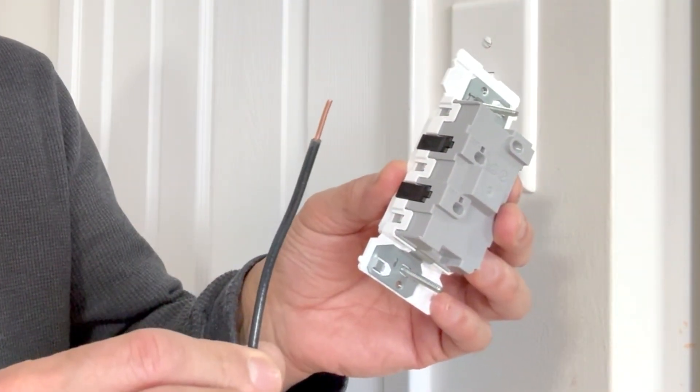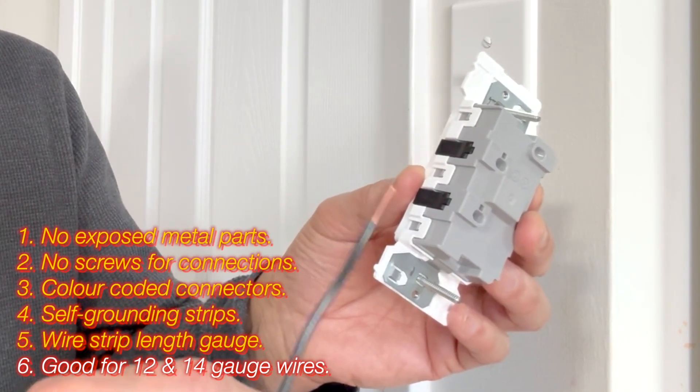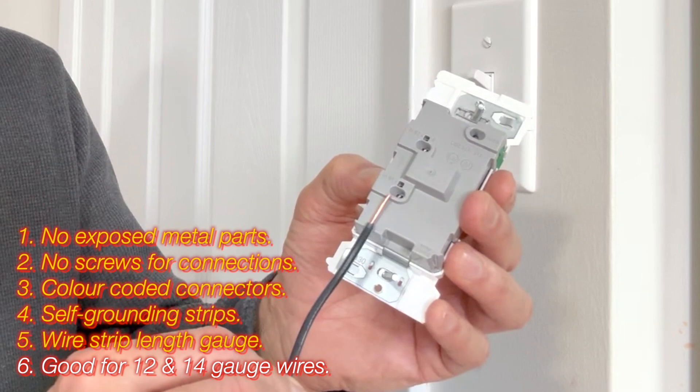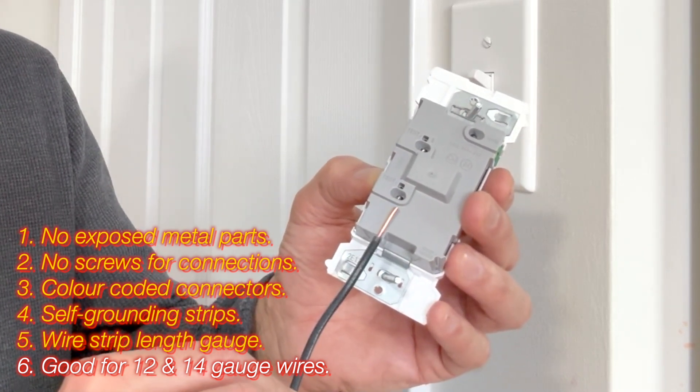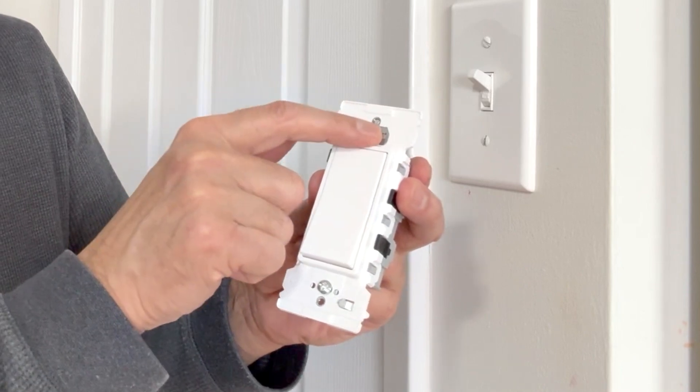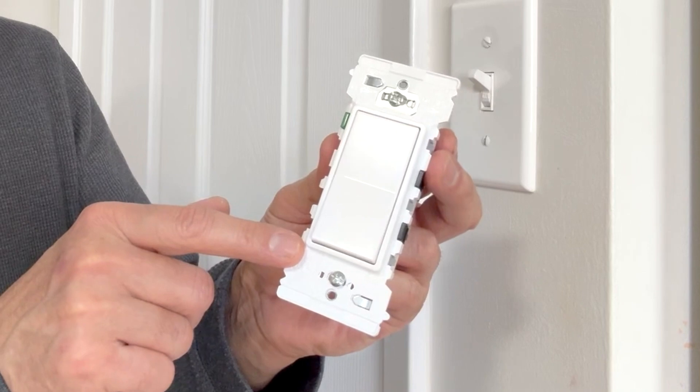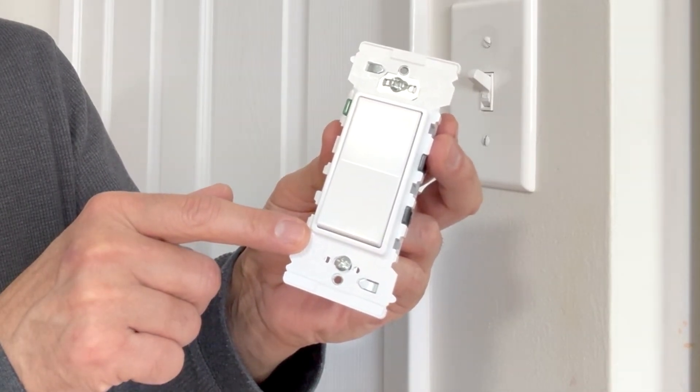This wire that I am using is a 14 gauge wire but this switch can also take a 12 gauge wire. So these holes are good for 14 gauge as well as 12 gauge wire. This switch is for AC only rated 120 volts 15 amps. If you see the marking upside down then you are installing the switch upside down.